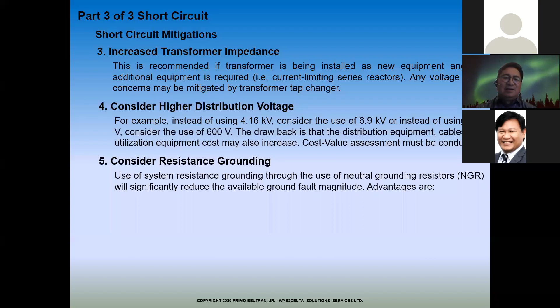Smaller bonding, smaller grounding grid. The only problem with NGRs is that because the ground fault current is low, your detection should use individual sensors and ground fault relays. That's an added cost. You save here but you have added cost there. So you have to look at it. The cost is almost the same but you have to look at reliability and safety. That's why NGR is more popular in industrial plants because they are able to sustain reliability and cost effectiveness by reducing the amount of copper against additional relays.